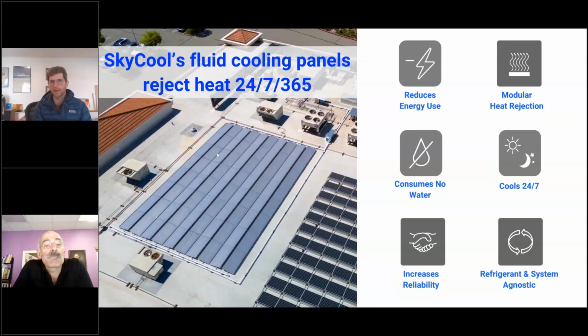But yeah, solar panels. We're using the same racking as the solar industry. It's attached to the roof the same way. We tend to use ballasted systems, but in places where you have high winds, hurricanes, and tornadoes, you need to have roof penetrations. There's no electrical connections in our panels. It's all hydronic, and so the labor is somewhat simpler. We don't have to work with the utility, for example, whereas with solar, you have to have an interconnection, and that can add delays and a lot of cost to projects, especially in places like Texas, or California, where you have a lot of backlog in these utilities.